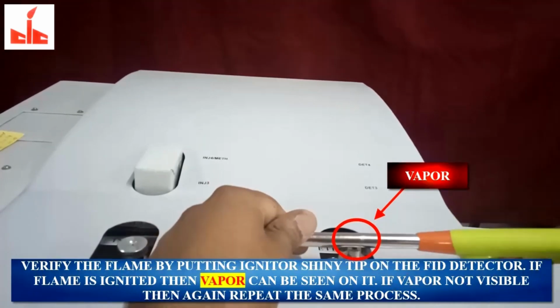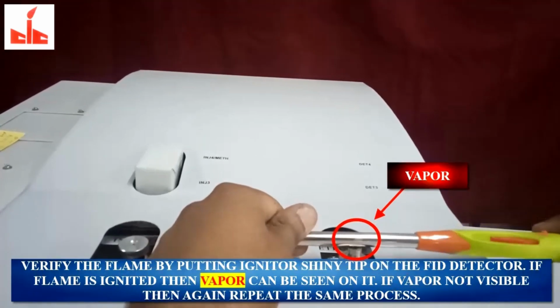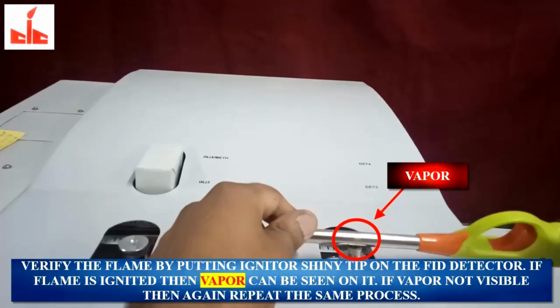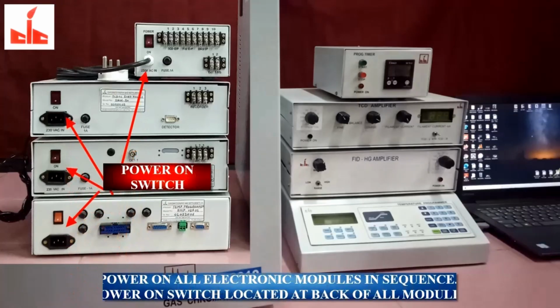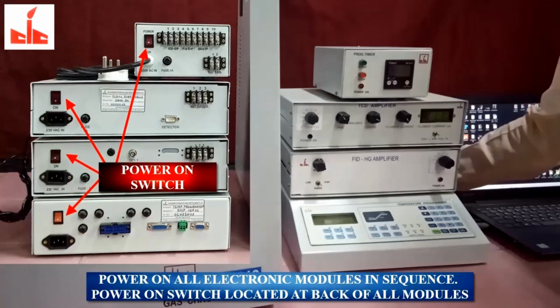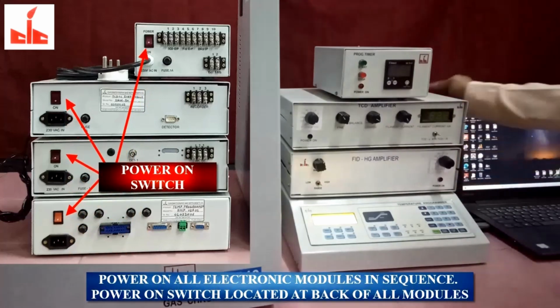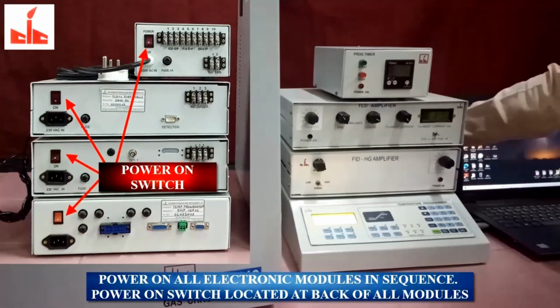Verify the flame, by putting igniter shiny tip on the FID detector. If flame is ignited, then vapor can be seen on it. If vapor is not visible, then again repeat the same process. Power on all electronic modules as per sequence. Power on switches are located at back of all modules.